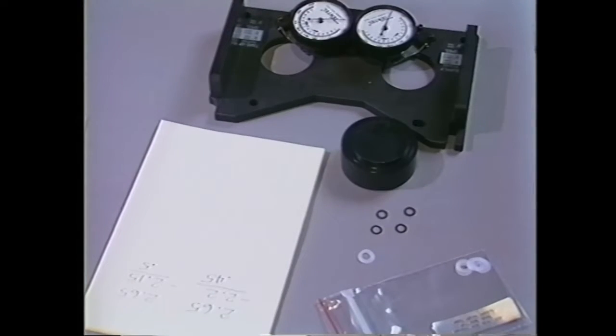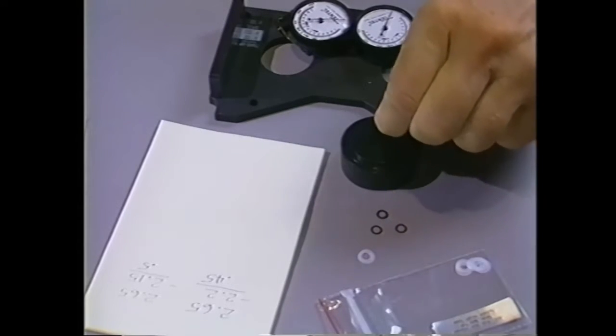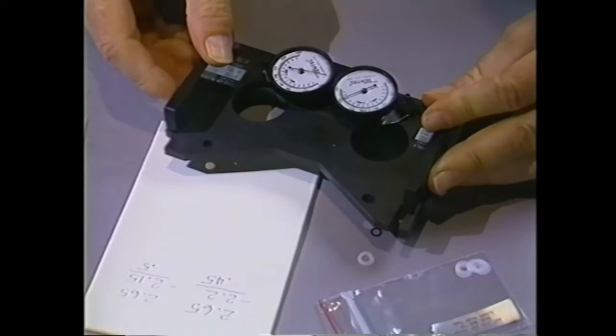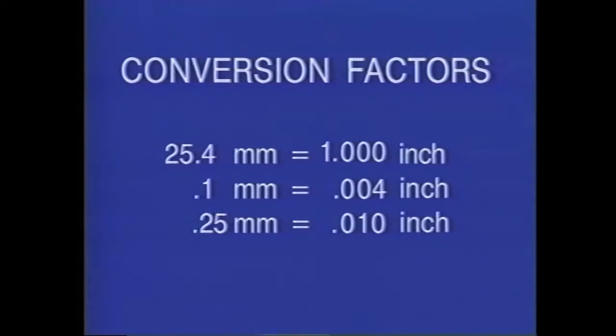Once it has been determined what shim thickness is necessary to raise or lower the spindle into the 2.15 to 2.20 millimeter specification, the proper shim thickness can be determined by placing the shim on top of the B7 master checking block and measuring the actual thickness using the B7 dial indicator. Here are some convenient conversion factors. 0.1 millimeters is equivalent to 4 thousandths of an inch. 0.25 millimeters is equivalent to 10 thousandths of an inch.